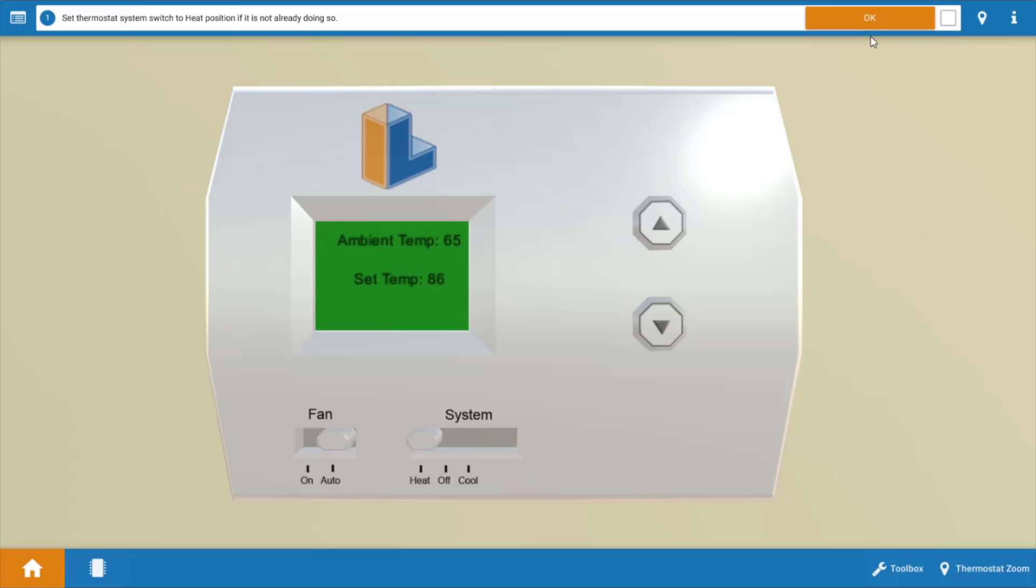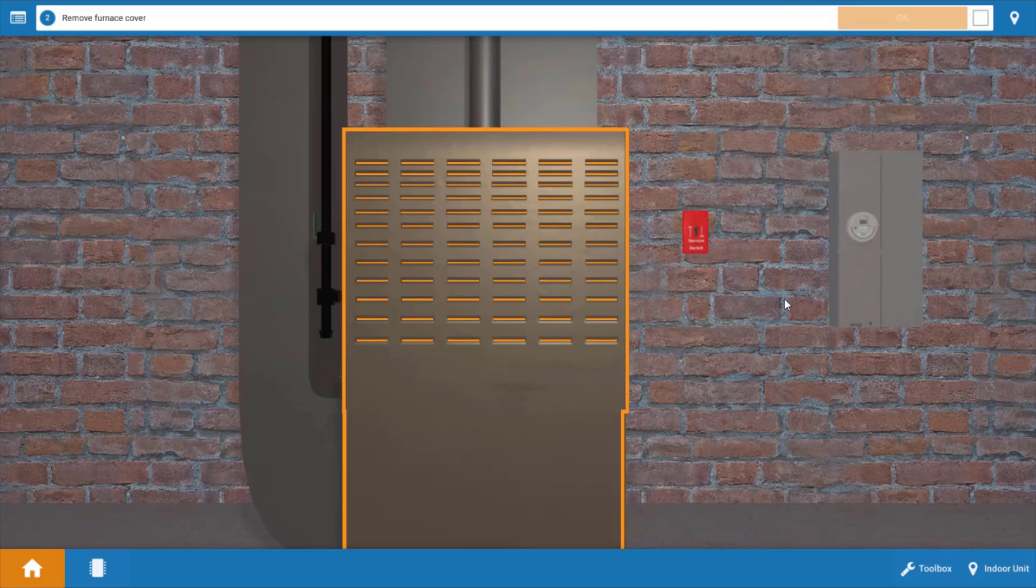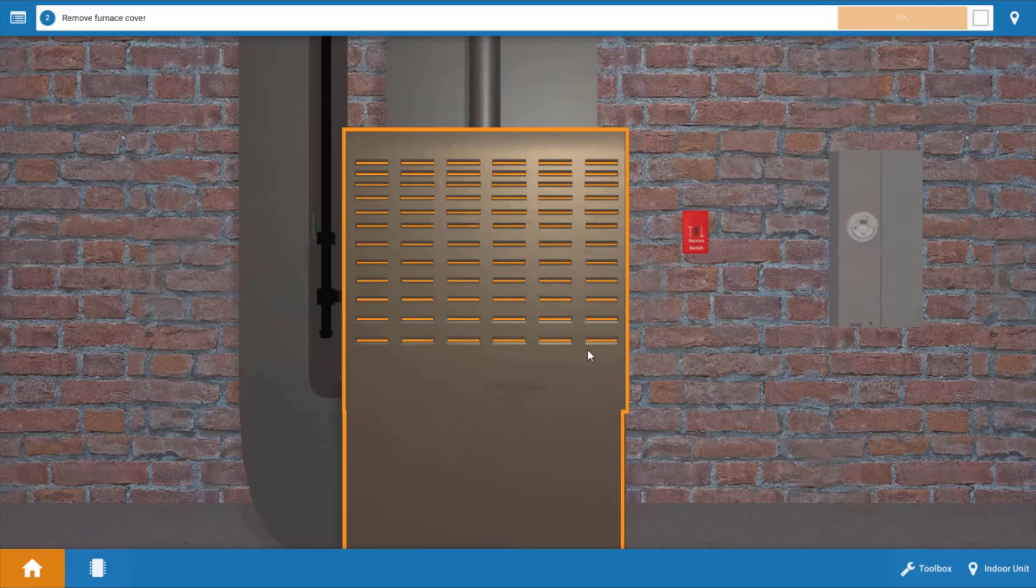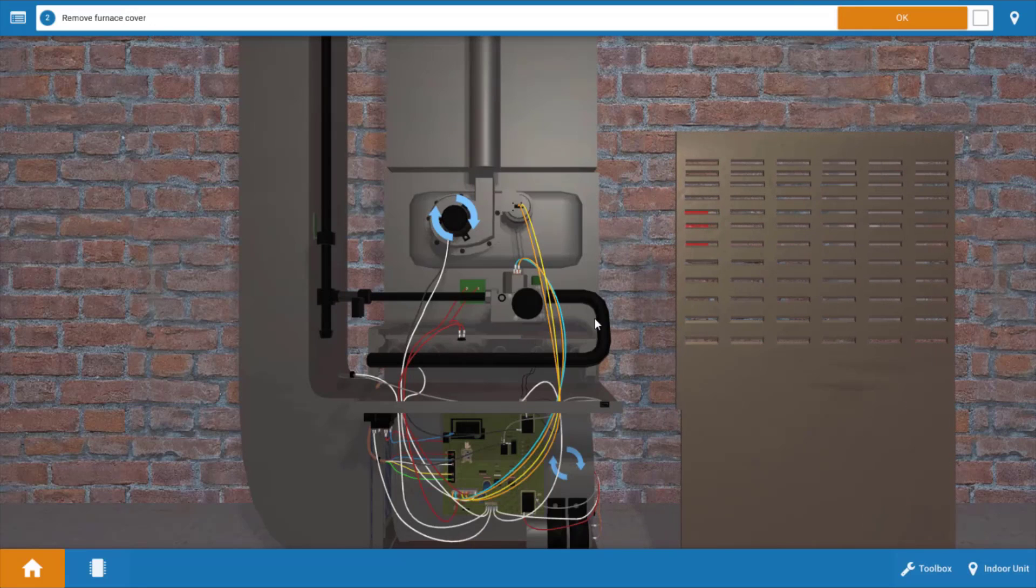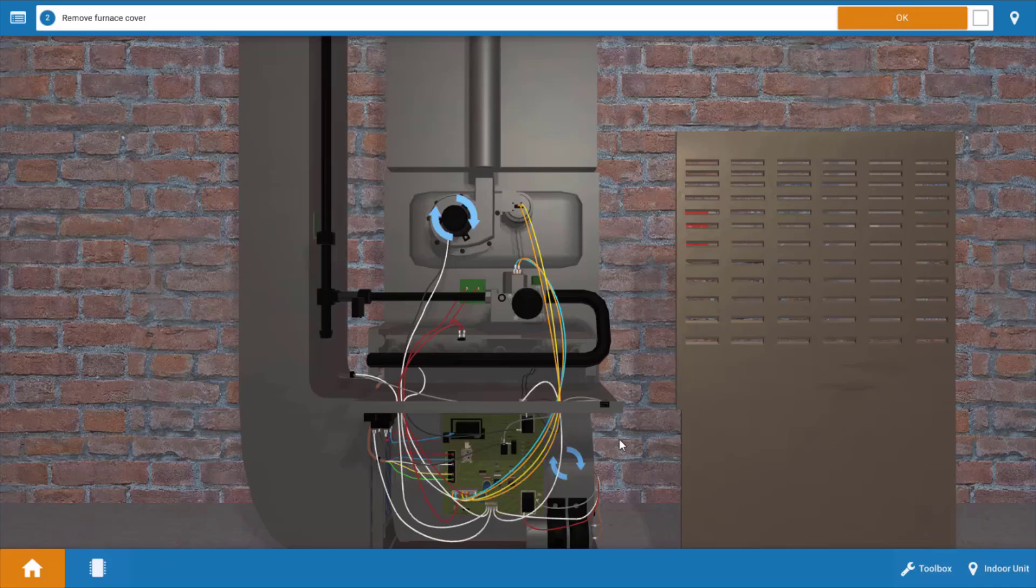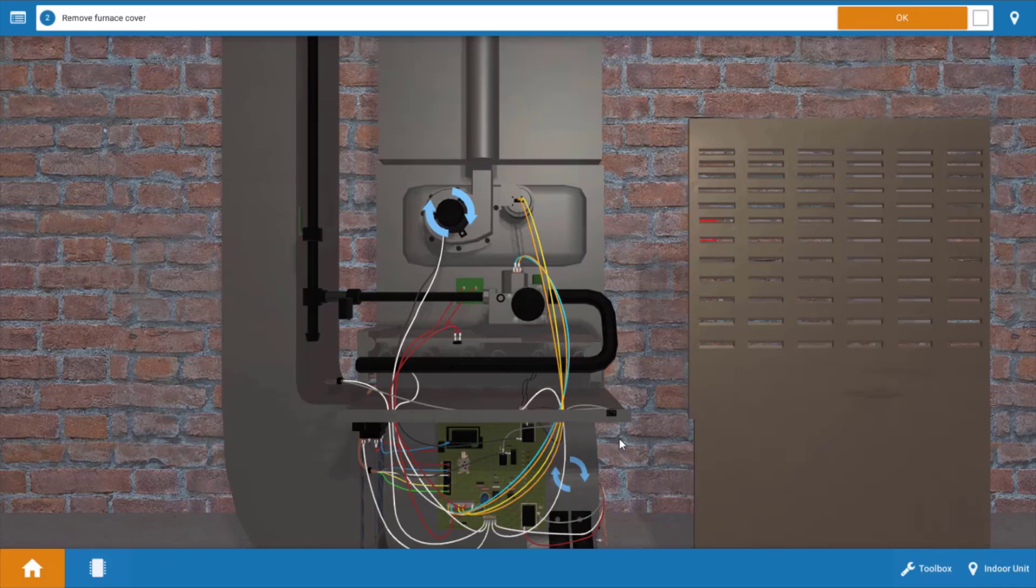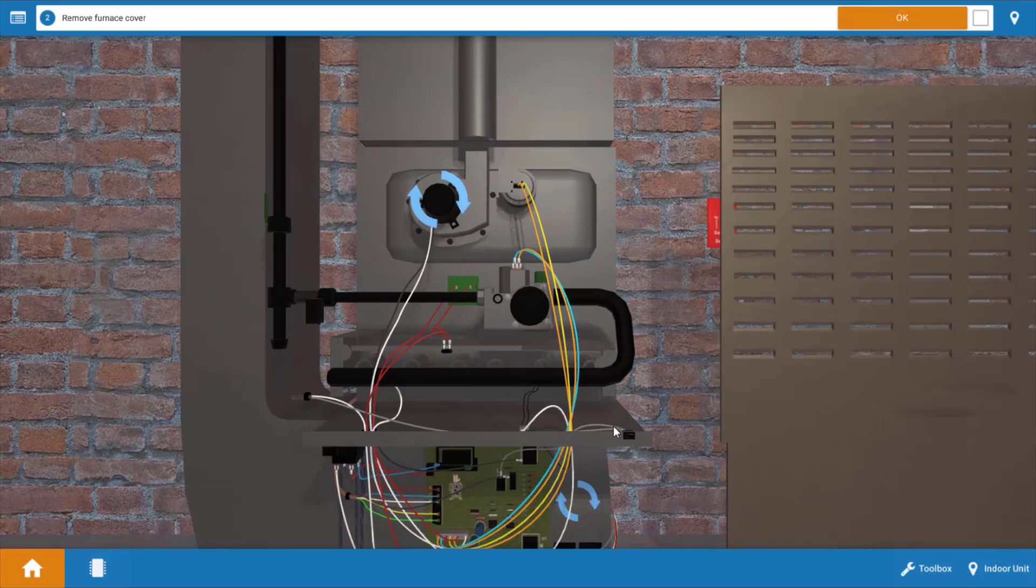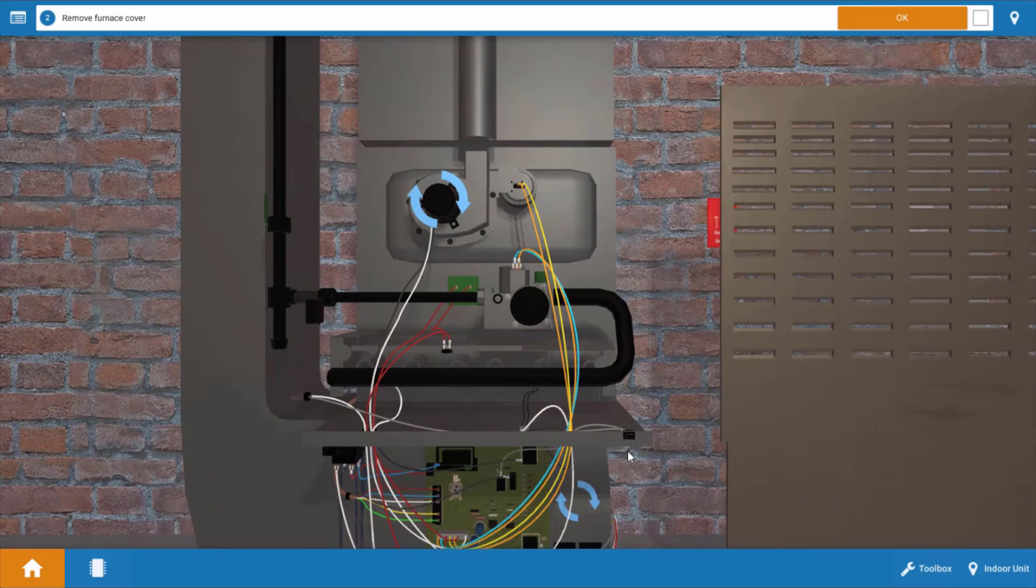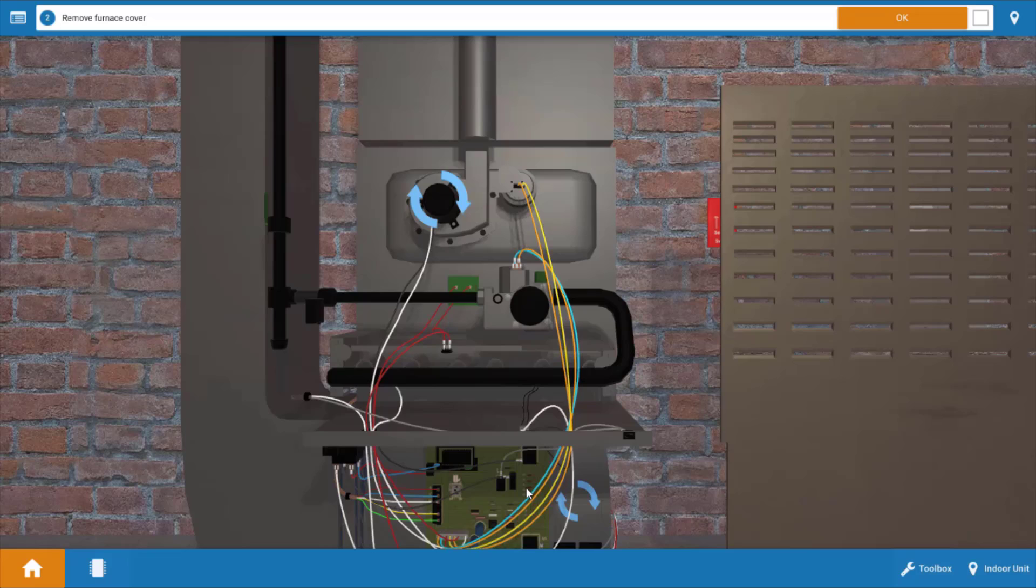Now after each step it's going to be necessary to click on the procedure guide up here at the top. Once we've done that we're going to remove the door from the furnace and take an inventory of which loads are running. But when we do this there's a door switch right here at the center right of the furnace and when the door is removed this switch is going to open its contacts and break power to the furnace.